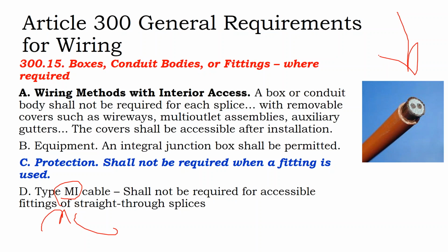And it's there so that that cable is becoming more robust. So it doesn't really matter if you put it in EMT conduit or a more robust cable. The point of code at that point is not anything to do with system grounding. It's just trying to give the cables more physical protection.